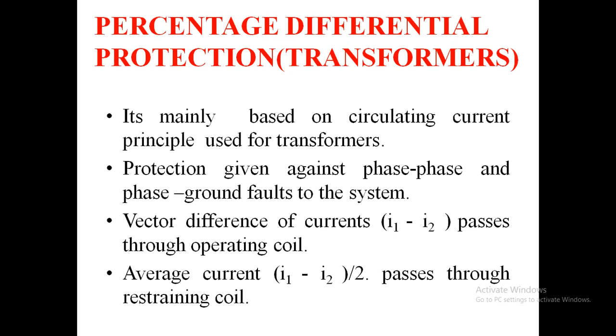So no current flows through the operating coil of the relay, but if there is a phase to phase fault or phase to ground fault, this balance gets disturbed. So this differential current flows through the operating coil, due to which the relay operates and trips the circuit breaker.